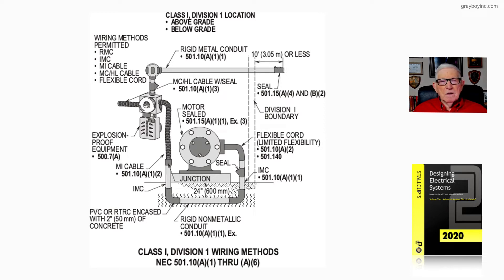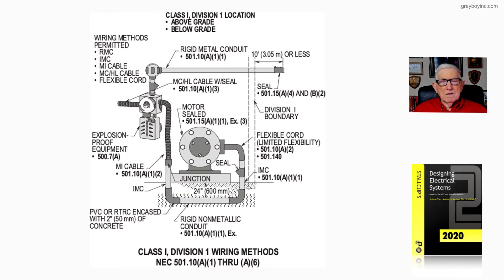If you're using flexible cord, that's covered under 501.140. If it's 24 inches in the earth, you could use non-metallic conduit in accordance with 501.10A1 item 1, but it's an exception. A lot of times you're going to encase it with 2 inches of concrete, and then use a metal elbow so you don't saw through the elbow when pulling in your wire. An MI cable can also be used as a sealing means in accordance with 501.10A1 item 2.